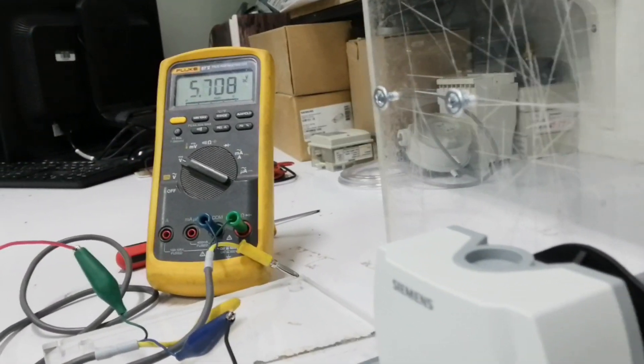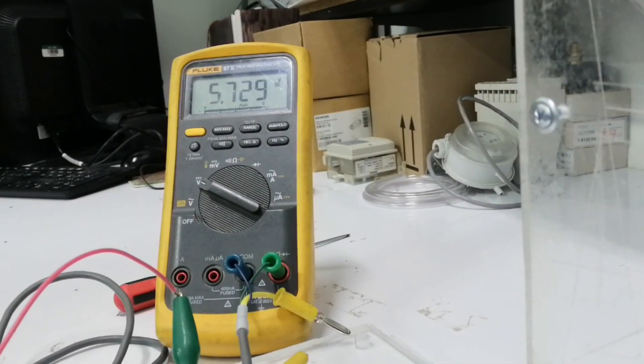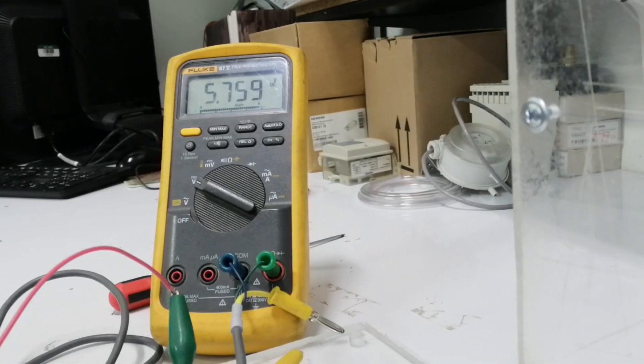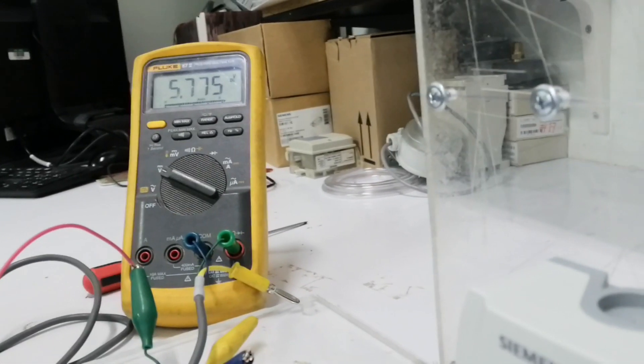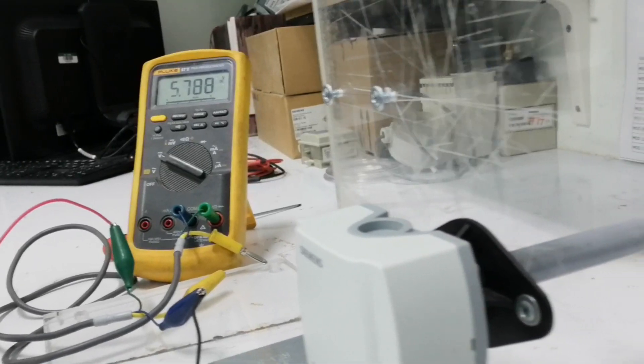The measuring current of systems or devices for acquiring the electrical resistance of the passive sensor differs greatly and impacts self-heating of the temperature sensing element at the end of the measuring tip. To compensate the impact, the passive output signal is simulated with an electronic circuit.